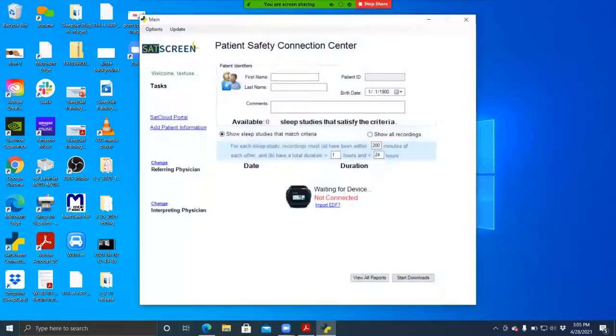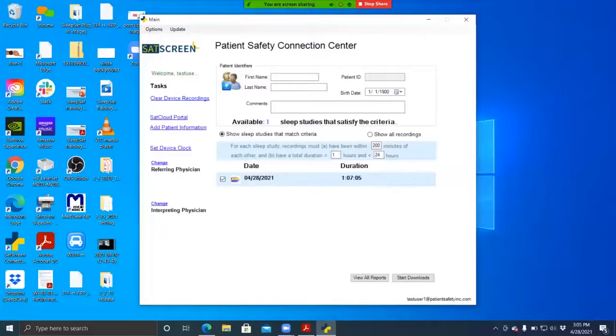How that looks is the SleepSat will display numbers counting down. Where it counts down from is depending on how much data is on the device. This device does not have much data on it. I'm going to change that. And as you can see, when it first connected, because these are the default values, it's not showing anything because we're currently in show sleep studies that match criteria.